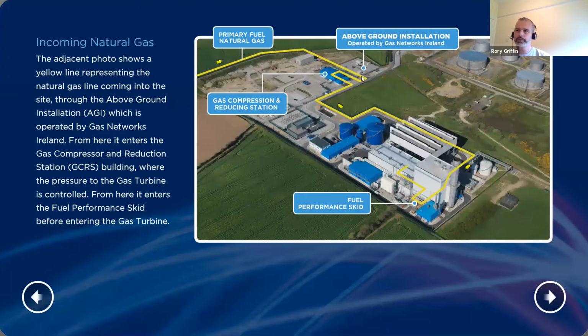So the gas comes in at, say, 58, 60 bar pressure. It comes through our reducing station and we drop it down to about 35 bar pressure for the gas turbine. So from here, it follows this path around the site. Just something to bear in mind, the gas itself, we actually have to preheat it up to 200 degrees Celsius. So we take intermediate pressure feed water, which I'll explain in more detail in a short while. So we preheat the gas fuel because as you drop down the pressure, you'll reduce the temperature as well. So the gas turbine is kind of high maintenance. It needs everything spot on. So this is the requirements we have here with the gas.